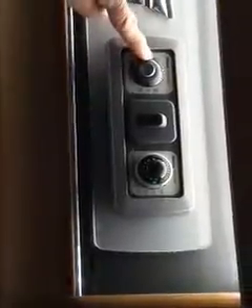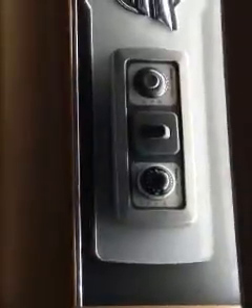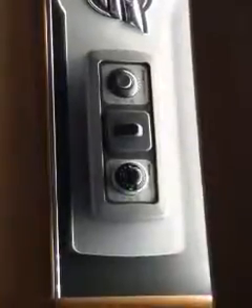On the gas side, if it fails you'll see a red indicator light come on. That indicates it has failed. The usual reasons are: one, you haven't turned your gas on; two, you haven't got any gas; or three, you've left that cover on — that will fail it as well. Or there may be air in the system.